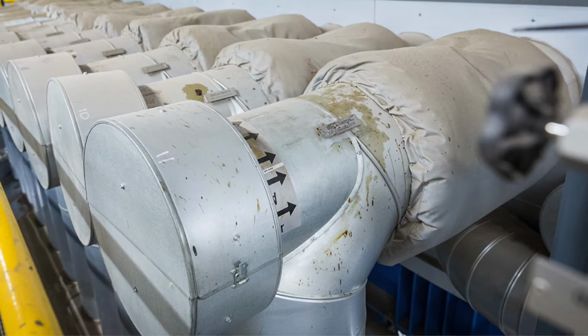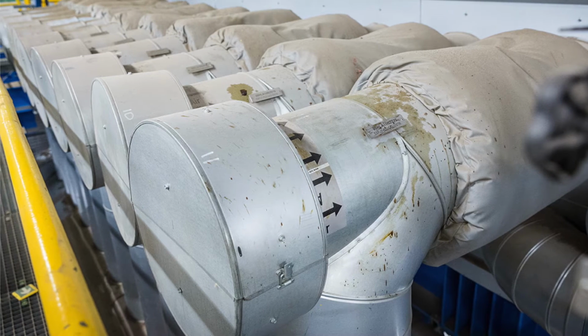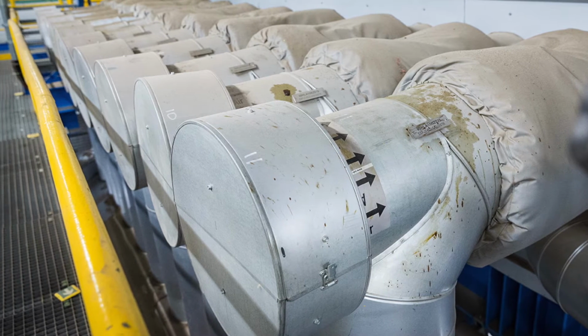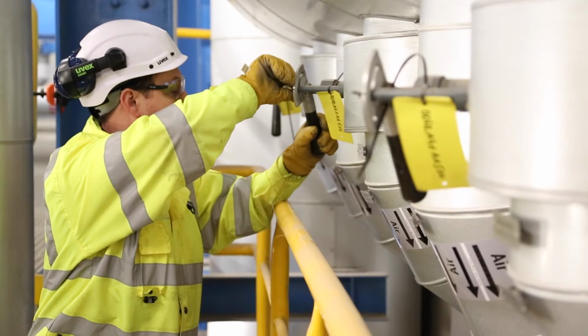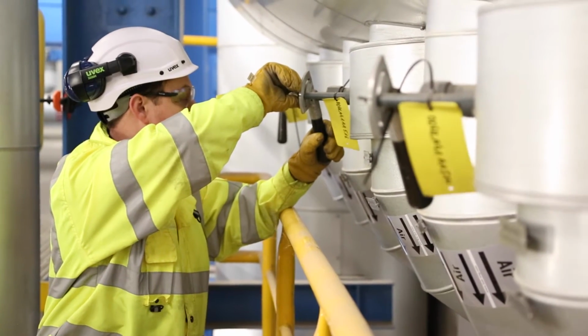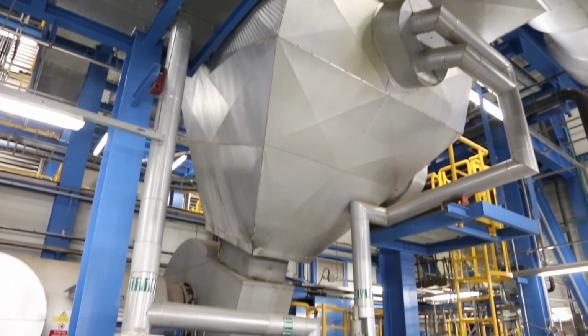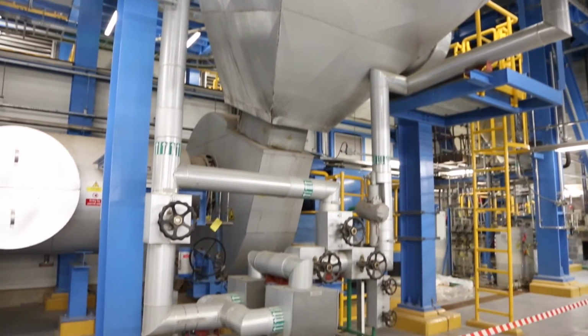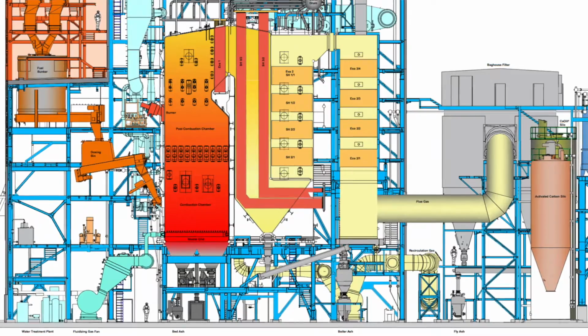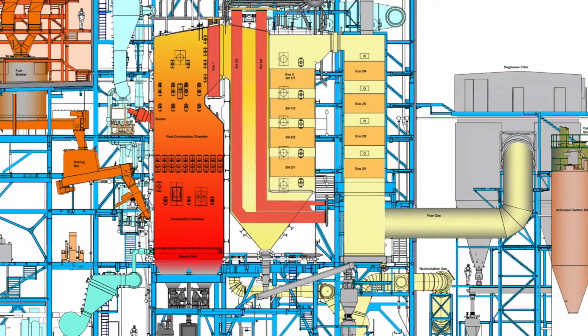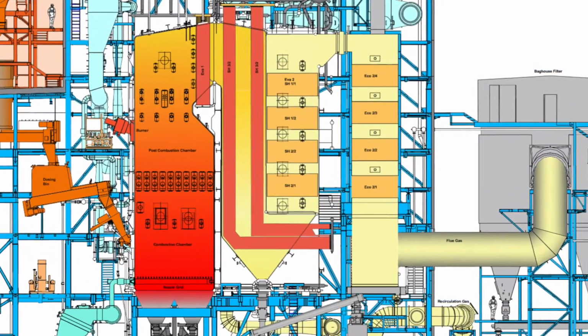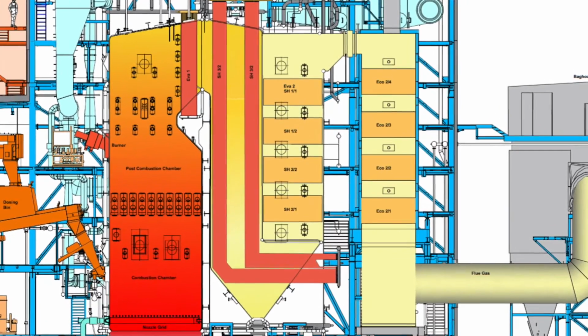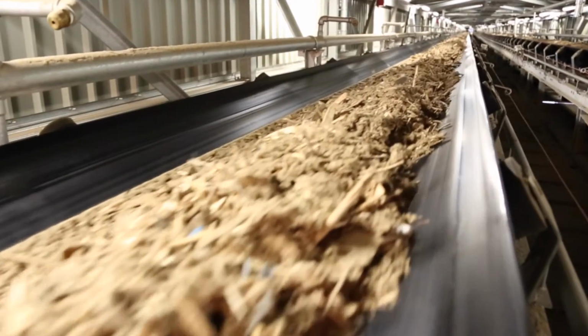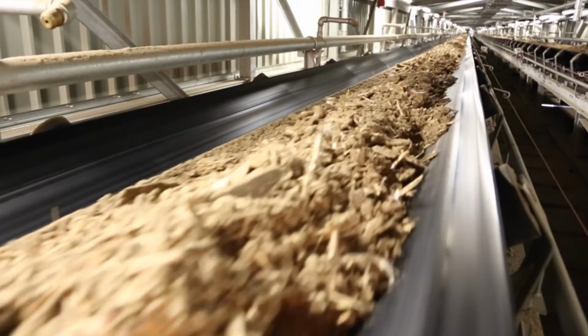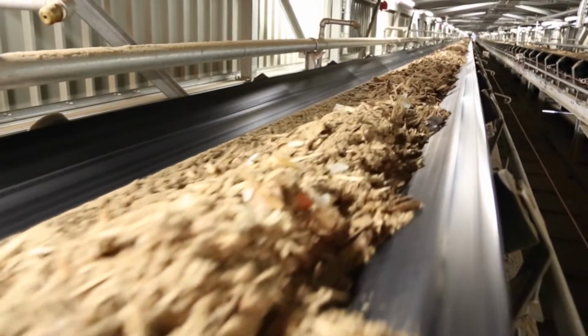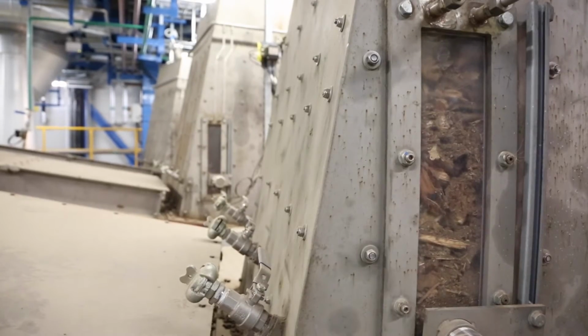The primary air enters the bubbling fluidized bed via the open-type air distributor. In order to maintain an optimum fluidization of the bed and a constant bed temperature, recirculated flue gas is added to the primary air upstream the air distributor. The concept warrants that the flue gas is cooled down sufficiently before it enters the first superheater bundles in the 3rd pass. The internal fuel handling system is based on Andritz's proven RDF feeding concept, which warrants highest availability.